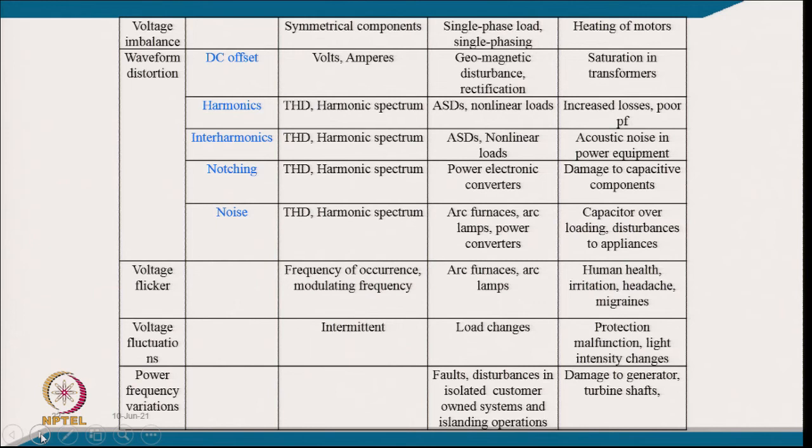Noise is quantified by THD and harmonic spectrum, caused by arc furnaces, arc lamps, and power converters, causing capacitor overloading and disturbance to appliances. Voltage flicker is quantified by frequency of occurrence, caused by arc furnaces and lamps, affecting human health — causing irritation, headache, and migraine. Voltage fluctuations occur due to load changes, causing protection malfunction and light intensity changes. Power frequency variation caused by faults may disturb isolated customer services like diesel generator sets and damage generators or turbines.